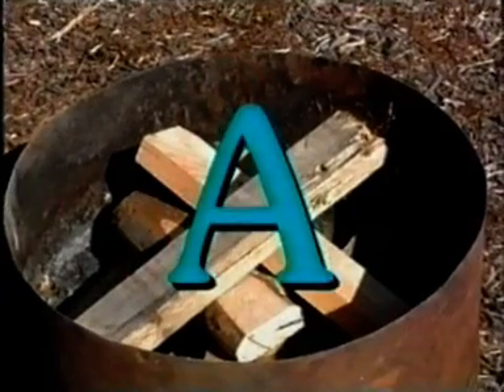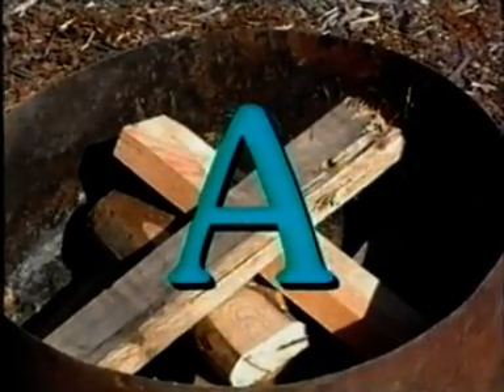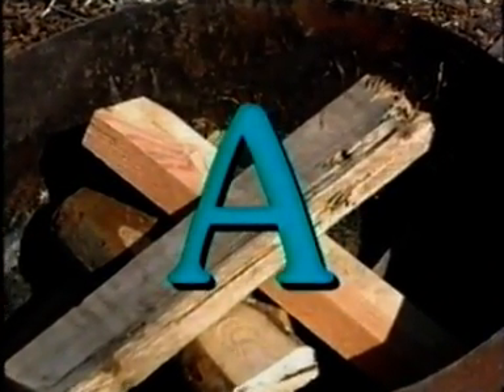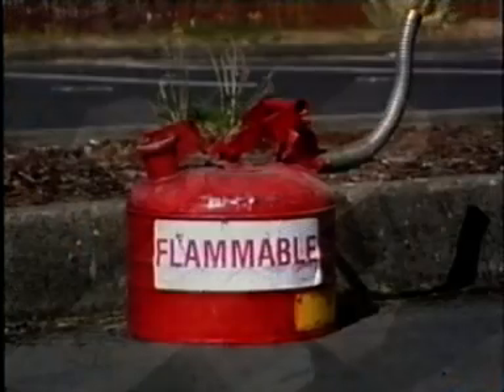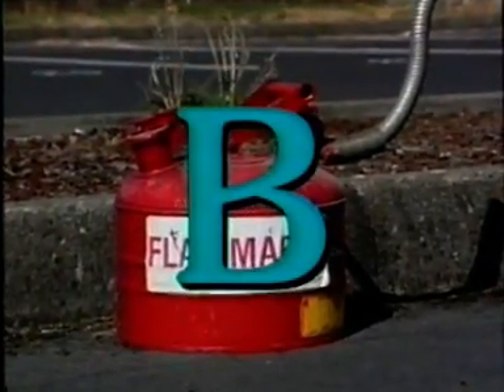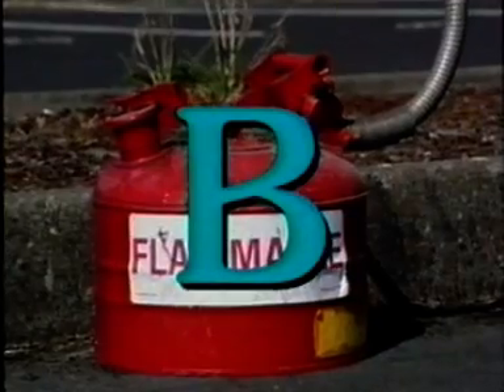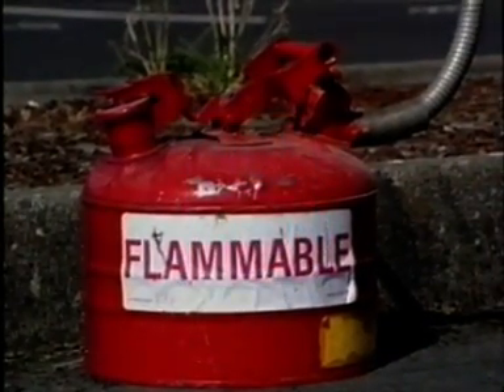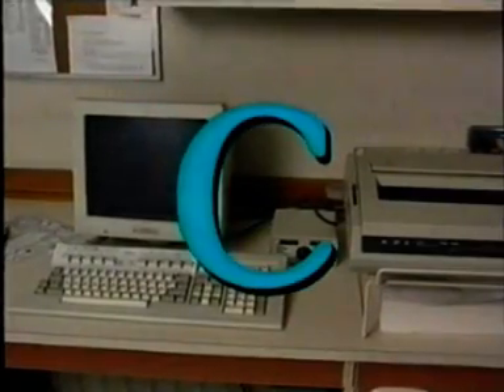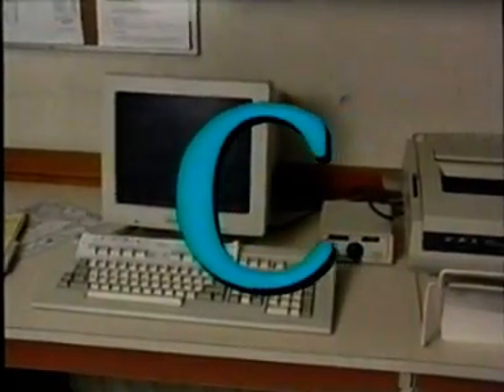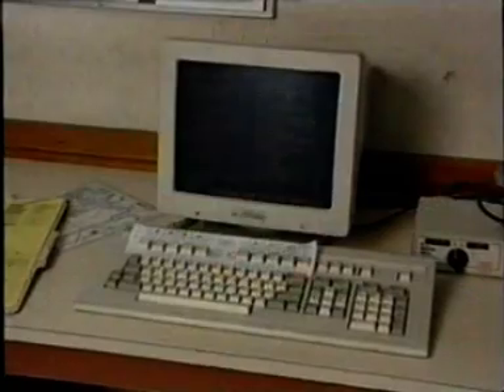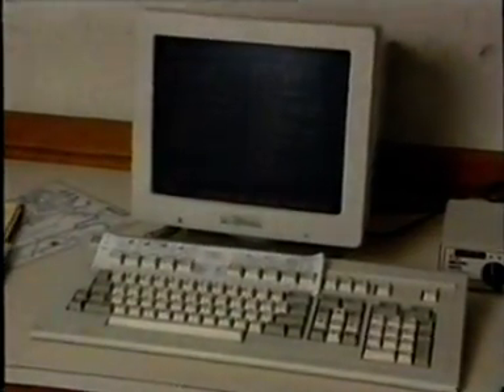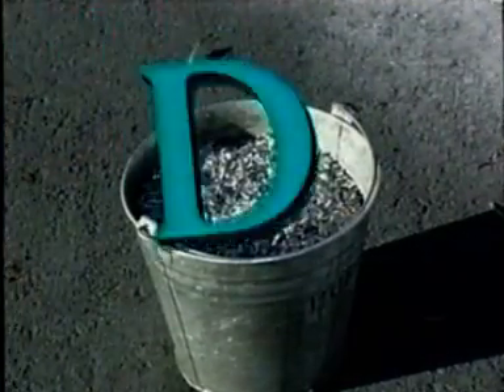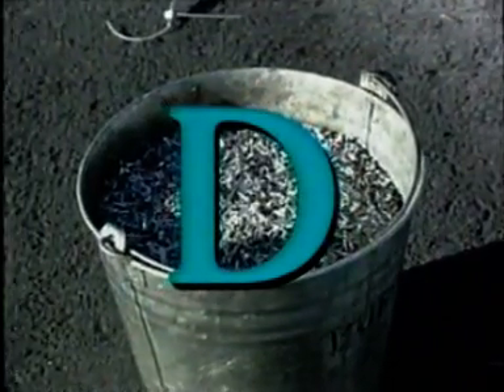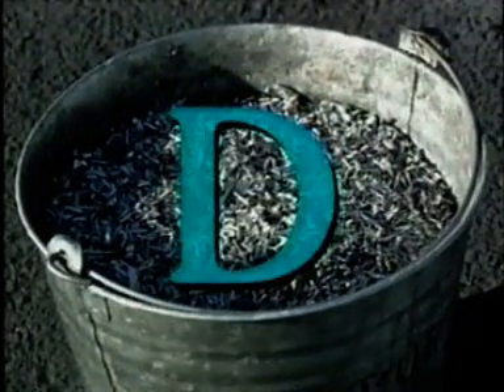Class A fires involve ordinary combustibles such as paper, wood, cloth, and many plastics. Class B fires involve flammable and combustible liquids and gases such as gasoline, oil, and alcohols. Class C fires are found in energized electrical equipment such as household appliances, computers, or overhead transmission lines. And Class D fires involve combustible metals such as aluminum, magnesium, and sodium.